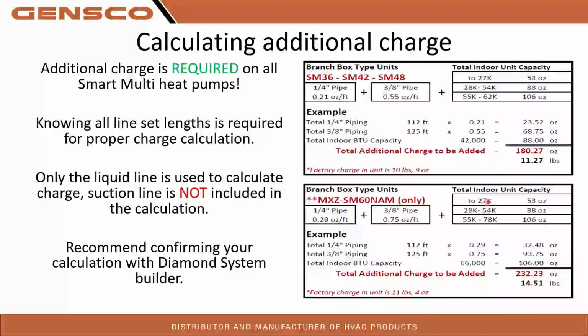So if you're less than 27,000 BTU, that would be 53 ounces additional charge. 28 to 54,000 BTU would be 88 ounces additional charge. And then 55 to 78 would be 106 ounces of additional charge. So what you do is figure out where you land in this chart. Let's say you're between that 55 and 78.